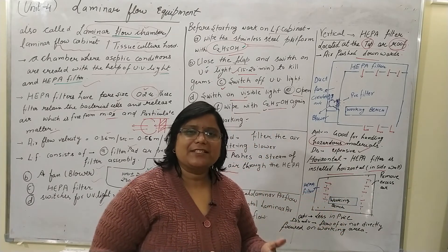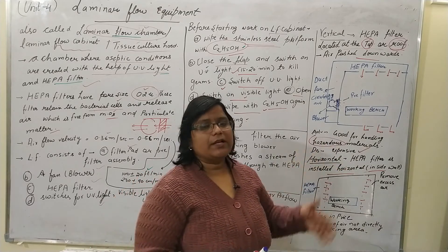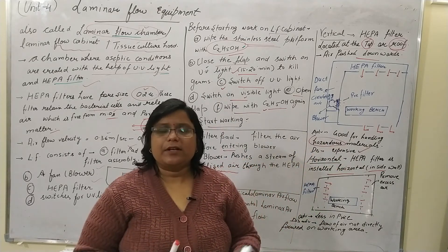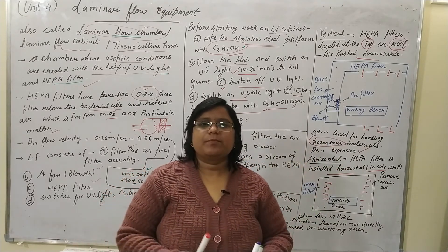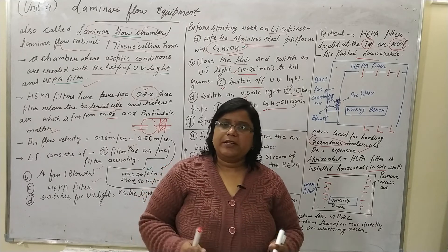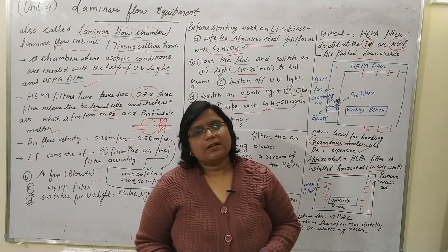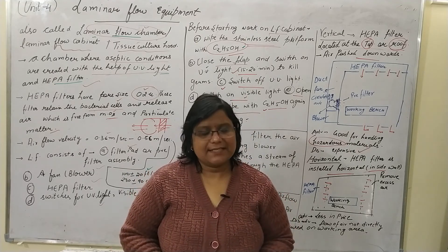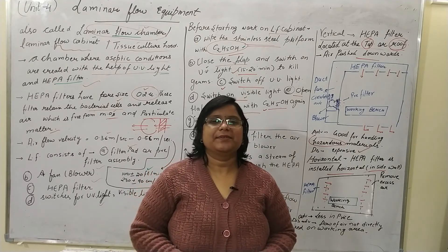However, horizontal laminar airflow is not suitable for hazardous materials because the airflow is not directly focused on the working area — it's not as safe as the vertical laminar airflow. I hope this is clear. If you have any doubts, please ask in the comment section; otherwise please like, share, and subscribe. Thank you.